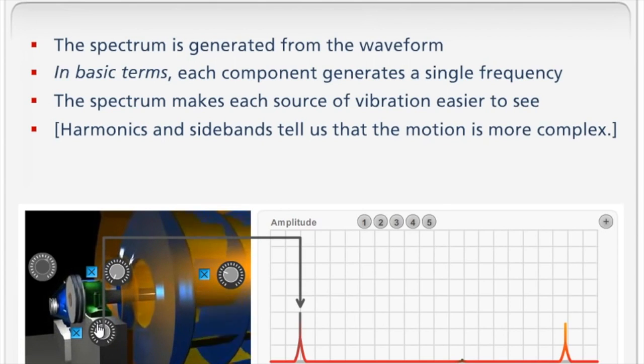But anyway, if I take one measurement, and then I come back later, and I see 30 days later it's like this, 60 days later it's like this, I can say, okay, the unbalance is growing. And I can decide whether I want to do something about this high level of vibration. Do I think this is going to cause the machine to fail? The structure to fail? Is it creating noise? Creating a quality problem or a noise issue for workers and whatever.